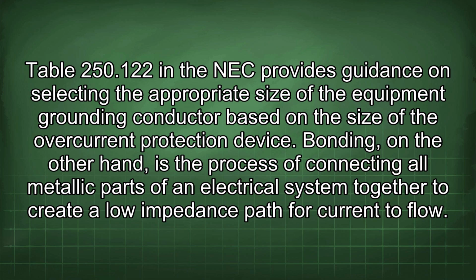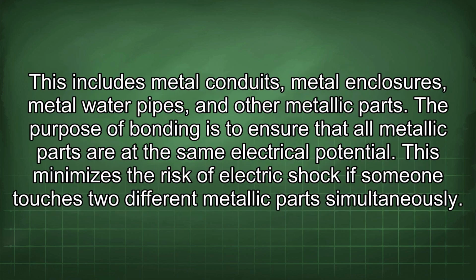Bonding, on the other hand, is the process of connecting all metallic parts of an electrical system together to create a low impedance path for current to flow. This includes metal conduits, metal enclosures, metal water pipes, and other metallic parts. The purpose of bonding is to ensure that all metallic parts are at the same electrical potential. This minimizes the risk of electric shock if someone touches two different metallic parts simultaneously.